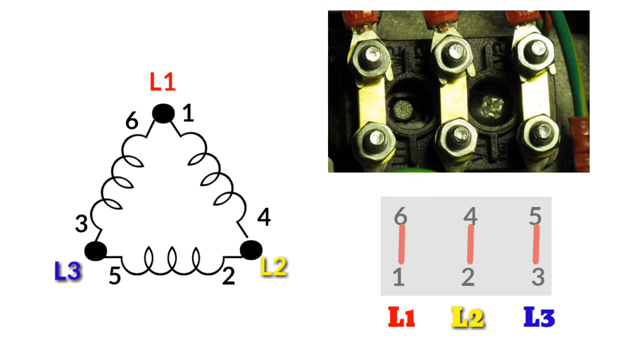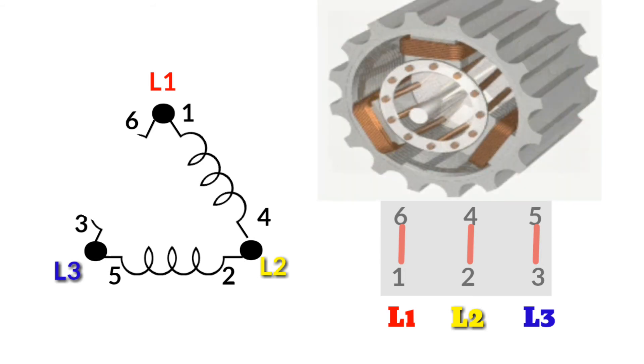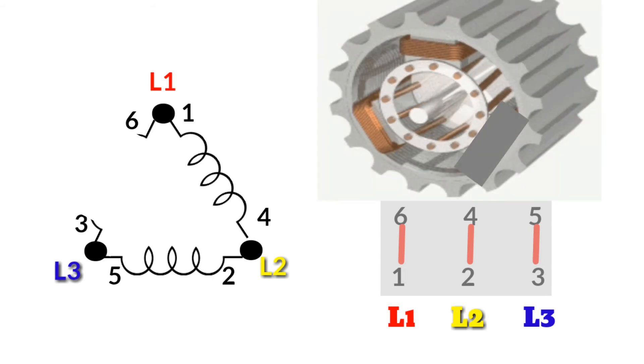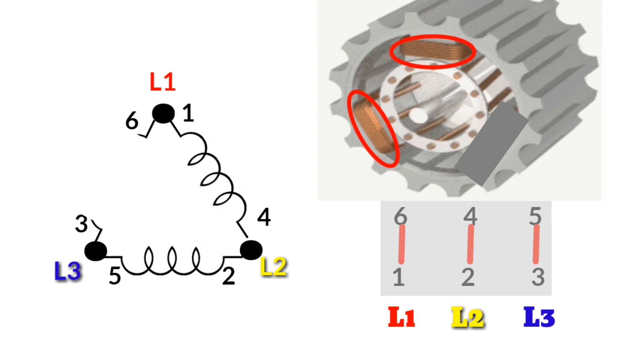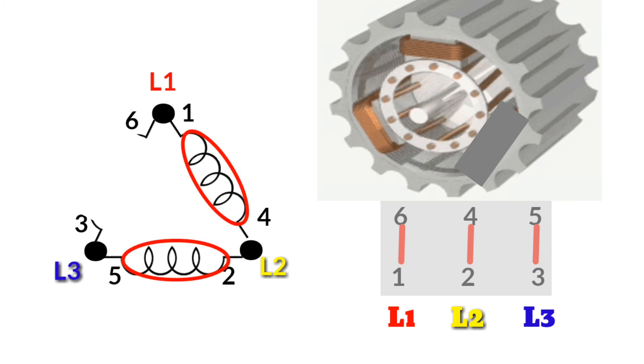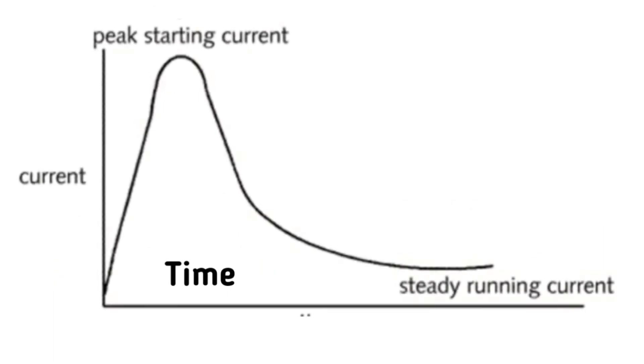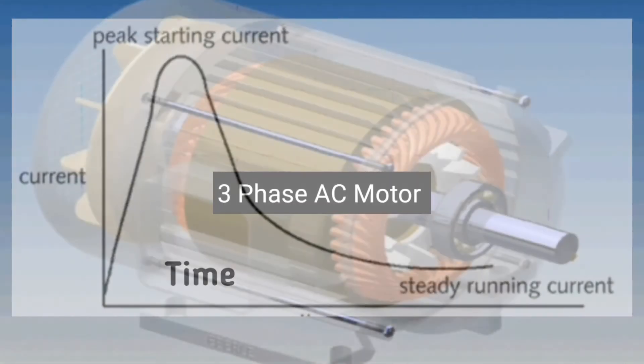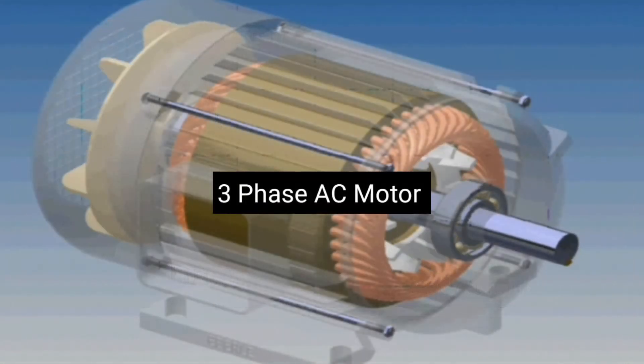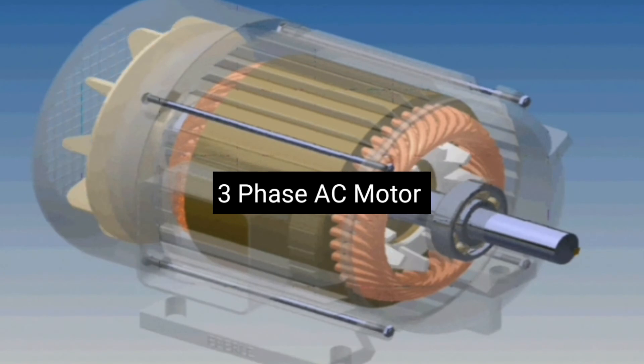An advantage of the delta connection is higher reliability. If one of the three primary windings fails, the secondary will still produce full voltage on all three phases, provided the remaining two phases can carry the load. The delta connection in a motor is used because it provides more power and starting torque, but the starting current is high. The star connection is used to reduce the starting current to get the motor up to speed, and then connect in delta for normal running mode.